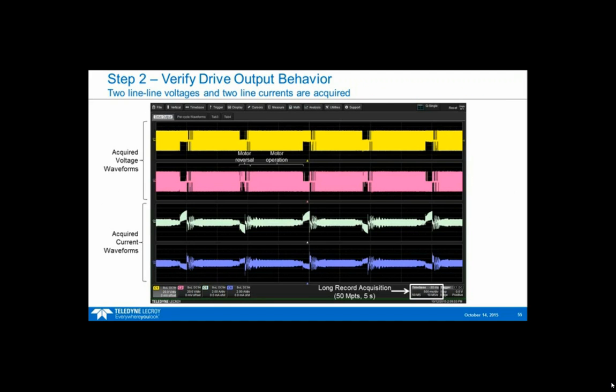Step 2, to verify the drive output behavior. Now we're getting into some power measurements. Again, the customer is using a 2 watt meter method in this case, so he's acquired 2 voltage waveforms shown right here. These are the 2 current waveforms. This is a longer acquisition. It's 5 seconds using 50 megapoints of data at 10 megasamples per second.